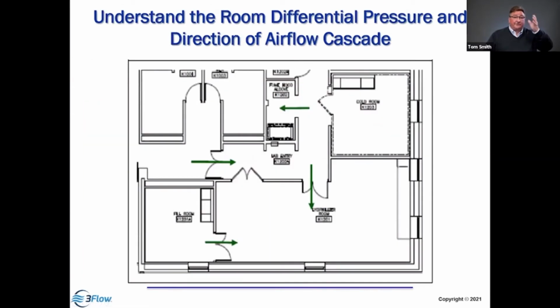We also have the room pressurization. When we're working in a space, it's nice to know if that room's under negative or positive pressure, because how can you test a fume hood if the room's not operating properly? So in this room over here, it's under positive pressure. It's blowing air out of that space. But this room is under negative pressure relative to this room and the corridor. So it'd be nice to have just a little bit of an airflow direction line to tell us where those airflow patterns should be coming from.